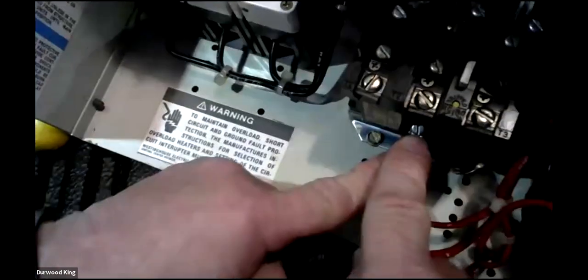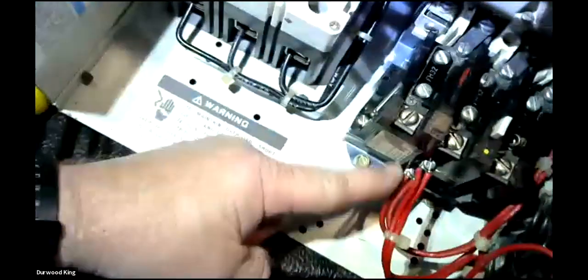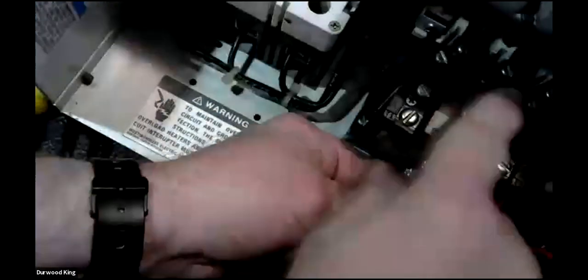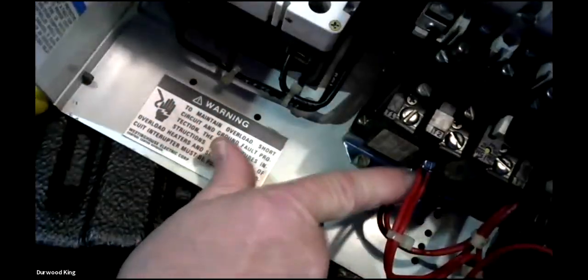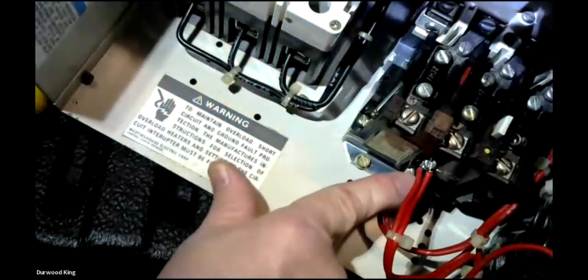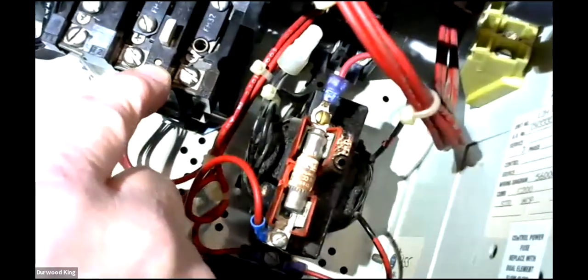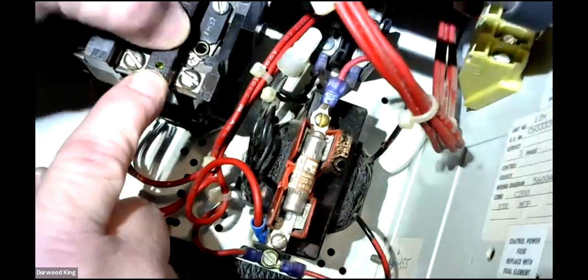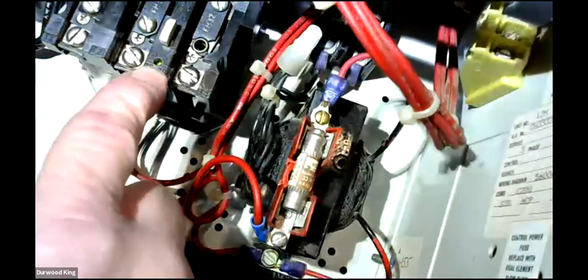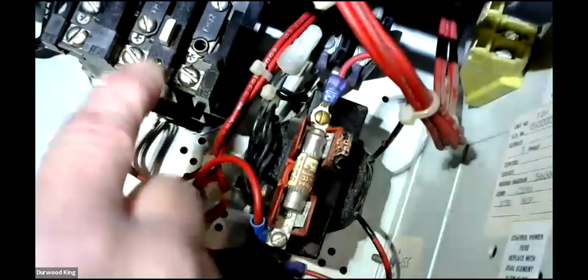Now, when it tripped, down here at the bottom, these two connections here, that's your normally closed contact right down there that you wire in with a coil. So when this overload trips, you lose a connection between this one. That would be like your 95 and 96 on what you've been doing. So that's your normally closed up under there, and it actually pops open, and you see that yellow indication in there? Mm-hmm. That yellow says you're tripped. Now, if I hit reset, the yellow goes away. You see that? It went back down in the hole. You see that? Yeah. So if it's tripped, the yellow comes up at you, and if you successfully reset it, it goes back down in the hole.